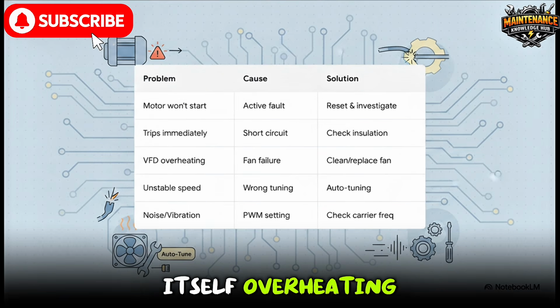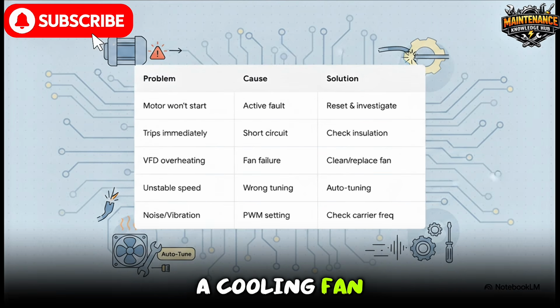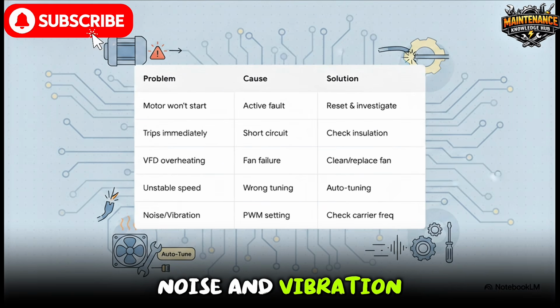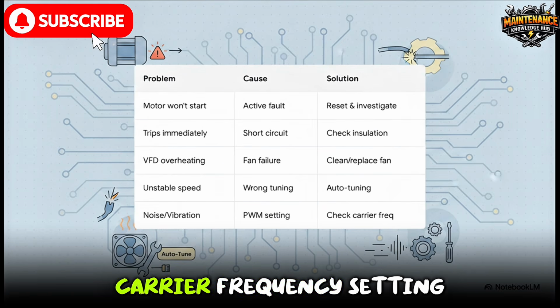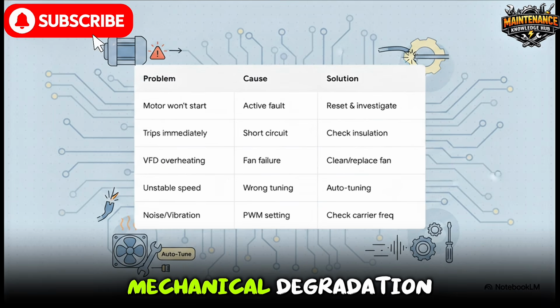Is the VFD itself overheating? It's highly likely a cooling fan failure. Just clean it or replace it. Experiencing unstable speed? You might just have the wrong tuning parameters. Run an auto-tuning procedure. Noise and vibration? That's often an issue with your PWM carrier frequency setting or just general mechanical degradation.